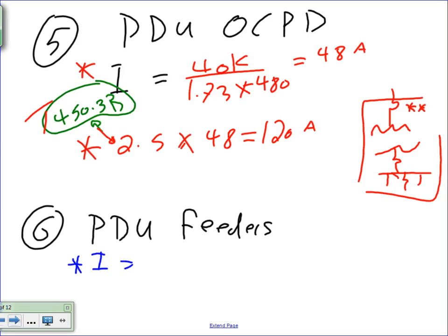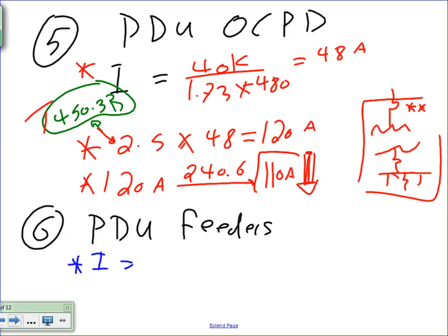Cool. Then you take the 120 amps, take this one to 240.6. What's the next standard down? The next standard down is 110, right? 110 amps. The next standard down is 110. Why down? Because if you go to this table, we talked about this, it doesn't allow you to go up. Why did I size the overcurrent protection device for this particular one higher? Because of the inrush.